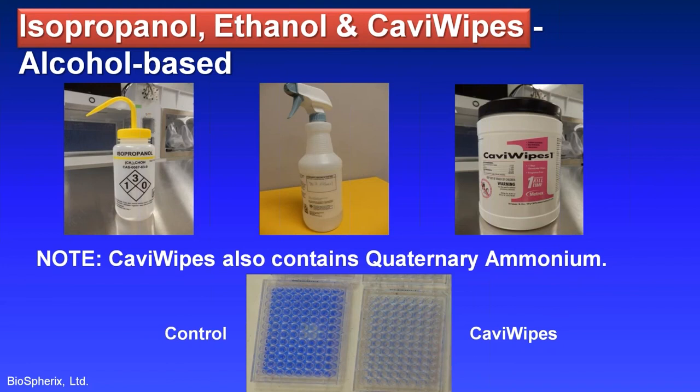So when you choose your disinfectant for use in the Xvivo system, please read the ingredients carefully. CaviWipes contain quats, but also have alcohol in them. Please try to avoid the ones with alcohol for use inside of the Xvivo systems.